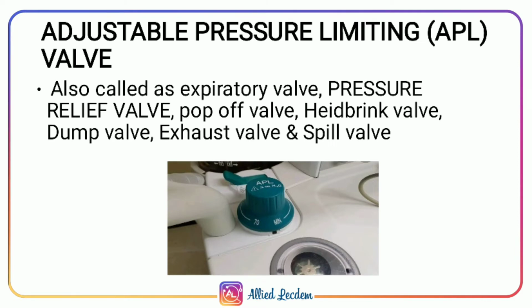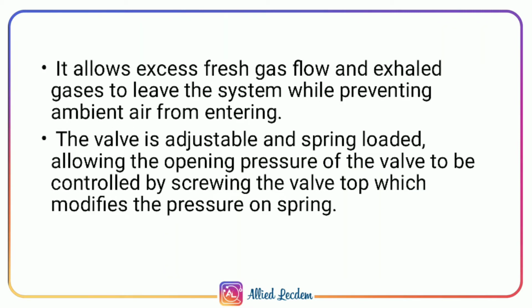Adjustable pressure limiting valve, shortly known as APL valve, also called expiratory valve, pressure relief valve, pop-off valve, dump valve, exhaust valve, spill valve, and Heidbrink valve. The major function of APL valve is that when there is an increase in exhaled gases or fresh gas flow, which is nothing but any medical gases or volatile anesthetic agent from the anesthesia machine, the APL valve makes those gases leave the system while preventing the atmospheric air from entering.